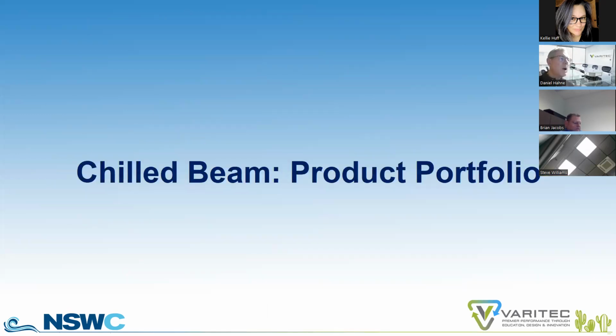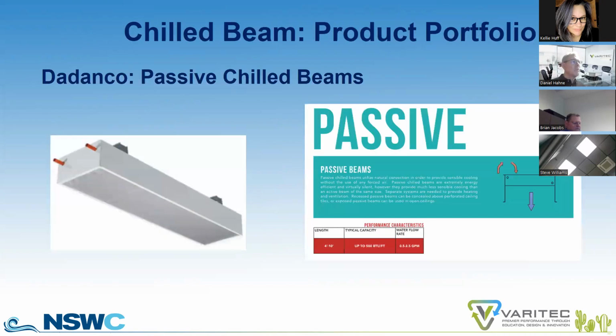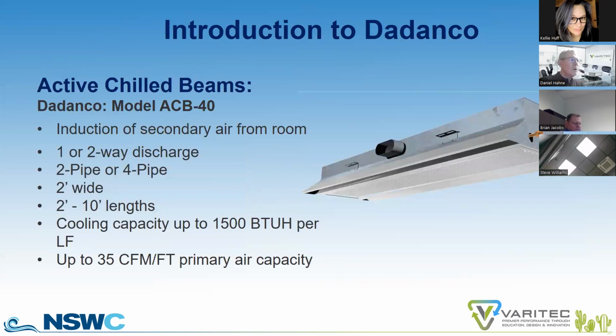So what type of products are available? What type of chill beam products are available in a building? Well, a passive chill beam, as I mentioned, is just that. It is a coil in the ceiling. You can provide customized casings. So if there are architectural features you want to provide with your beam so it blends more seamlessly into the visual aesthetic of a room, we can look at that possibility for sure. But again, the technology is simply a chill water coil located in the ceiling of a room.